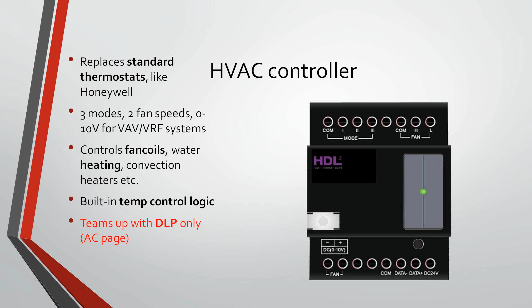It has 3 modes, which is heating, ventilation, and cooling. It has 2 fan speeds, high and low, and it has 0-10 volts down here, output, for VAV VRF systems. It controls fan coils for buildings, but if you use it at home, it can control water heating or convection heating. So we mostly use it for heating, actually. It has a built-in temperature logic, but keep in mind that it teams up with DLP only. So they only work together. They will not work separately. Yes, keep this in mind.